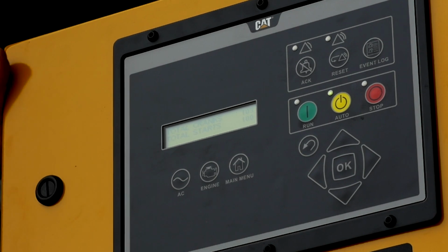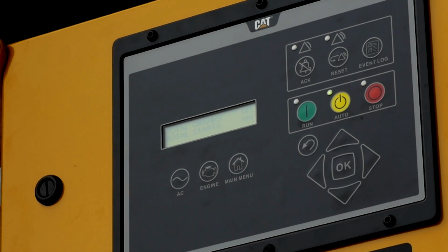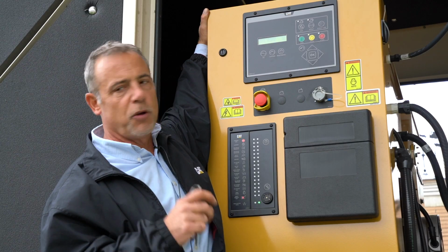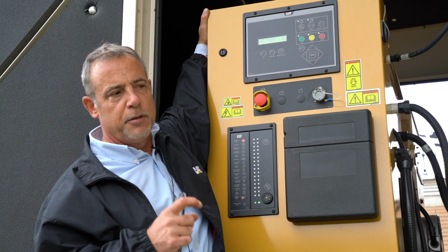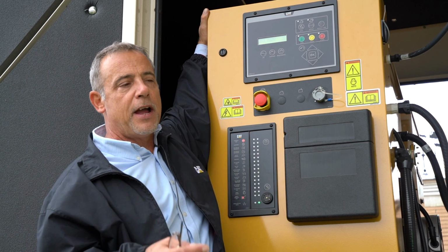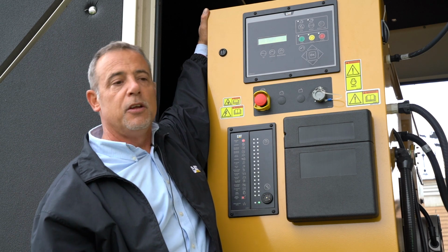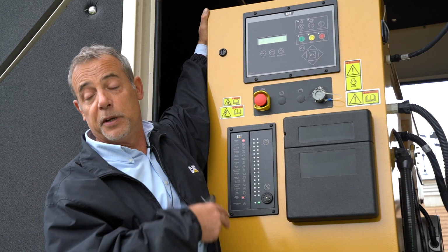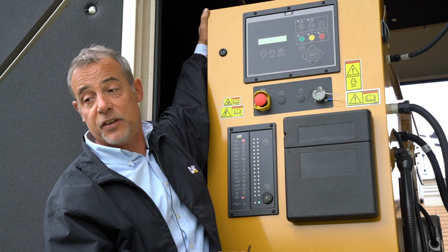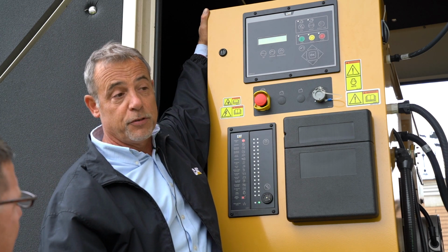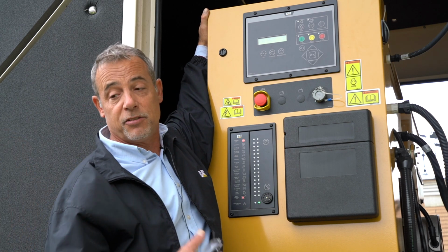Your next page will give you your total: how many times this thing went through a crank cycle and how many times it actually started. There's always a difference between the two because first off, in the factory, they check it to make sure it goes through a crank cycle before it fires up. We put it through a crank cycle to make sure we get the alarm as if it didn't start, for an overcrank. And anytime you change your fuel filters on this thing, you're probably going to have to go through a couple of crank cycles just to prime it.